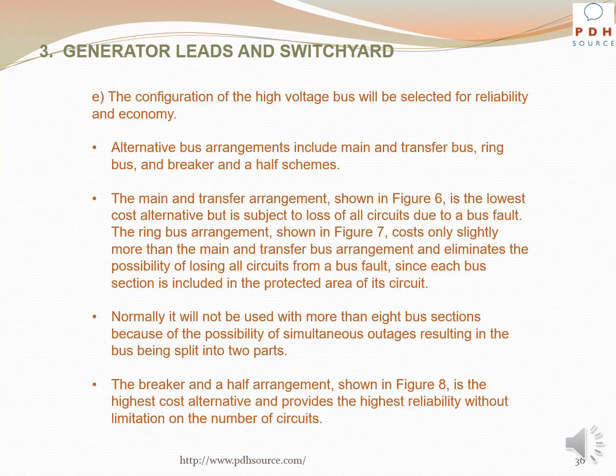The configuration of the high voltage bus will be selected for reliability and economy. Alternative bus arrangements include main and transfer bus, ring bus, and breaker and a half schemes. The main and transfer arrangement shown in Figure 6 is the lowest cost alternative but is subject to loss of all circuits due to a bus fault.